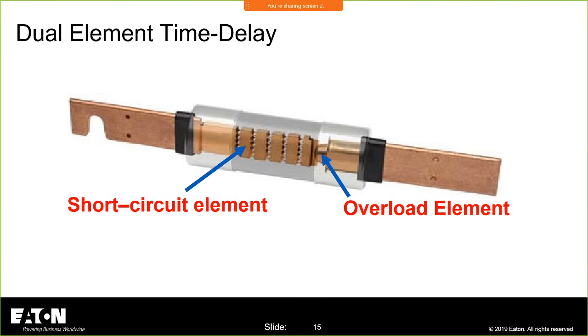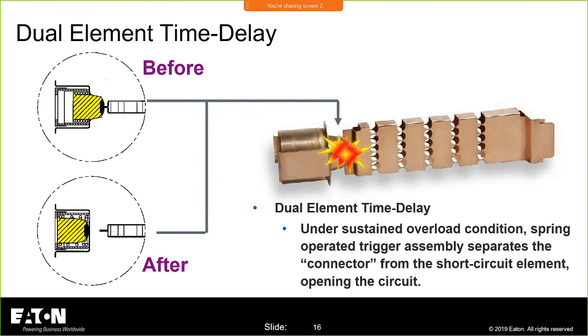And when you open one up, this is what you see. You're going to see an element that has a bunch of pinch points. And then you're going to have another element that looks like it has a little solder, like a little silver unit to it. I think the cube fuse, and I laugh because it almost looks like a little piece of chewing gum sitting in there. It's just a portion that gives you the long time thermal capabilities because you're melting something. And in that little part, you have a little nub that's spring loaded. It's connected by a very tiny pin, I would call it, that when it melts, it opens and clears the fault. And that is a long time delay.